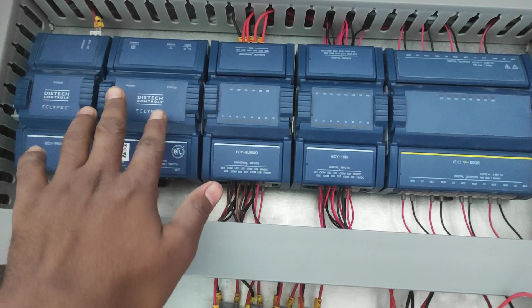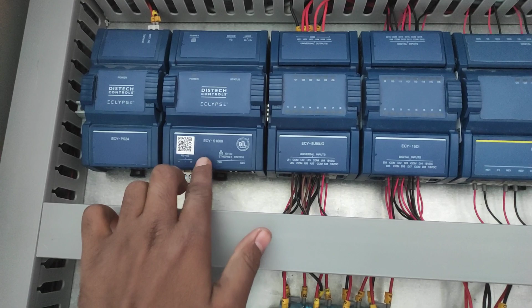So with the help of this device we can attach up to 12 cards. More than 300 input outputs we can connect with this controller, this communication unit. This is actually placed inside the chiller panel section. In the chiller panel section, we are controlling different types of valves, temperatures, and the chiller pumps. All things are controlled by these controllers.